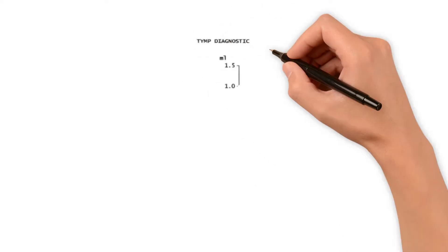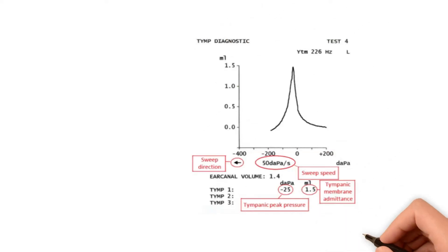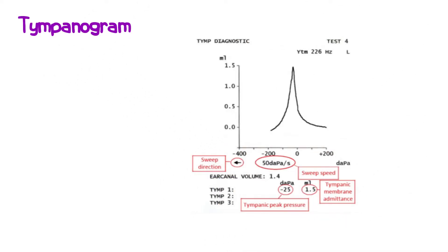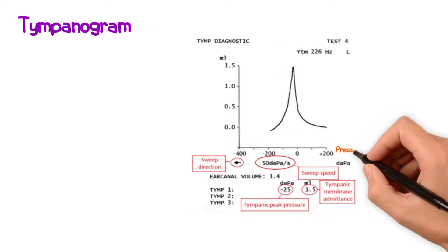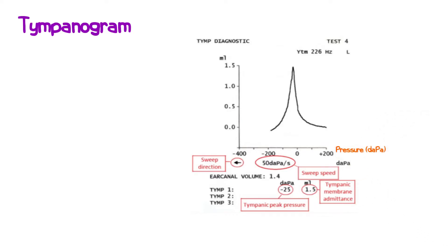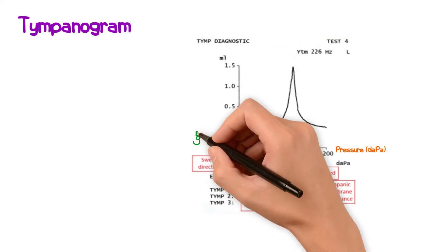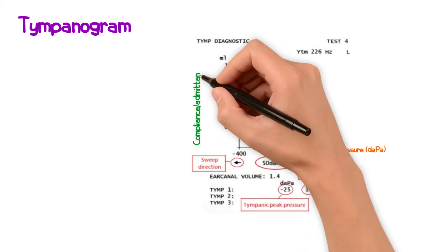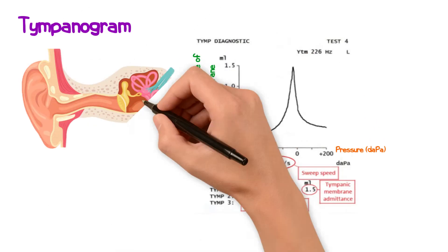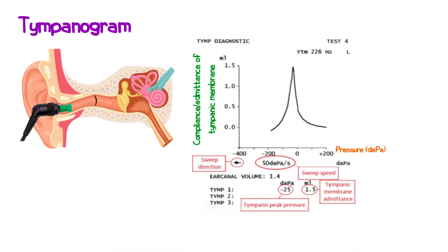The results of tympanometry are plotted on a graph known as a tympanogram, where the x-axis represents the pressure measured in decapascals and the y-axis measures the compliance or admittance of the tympanic membrane — that is, the amount of sound energy admitted into the middle ear.